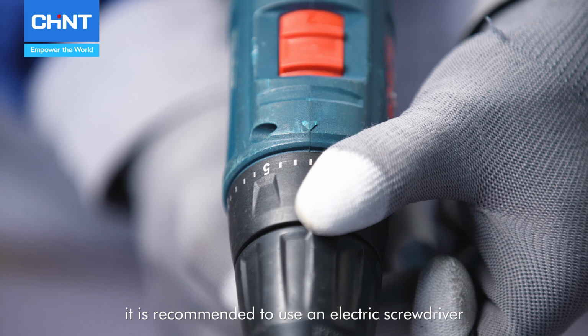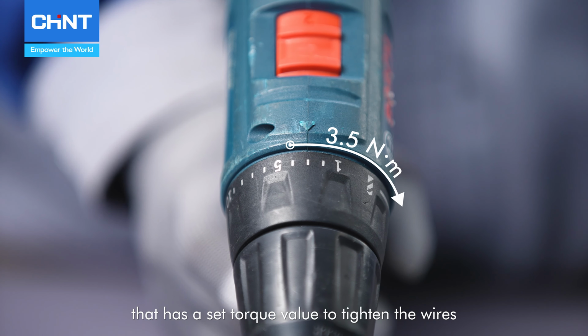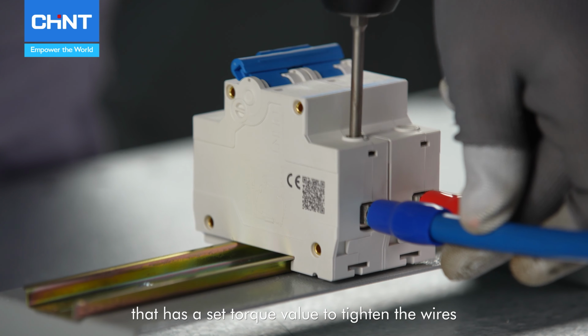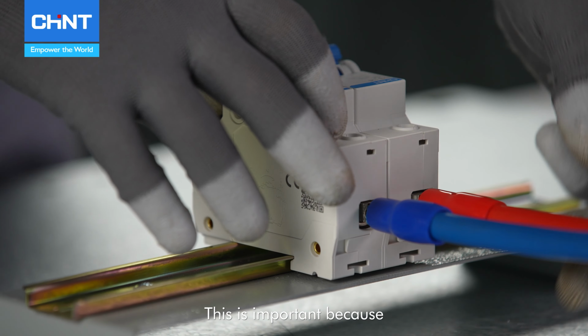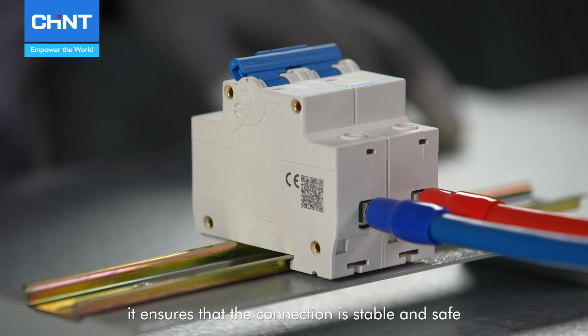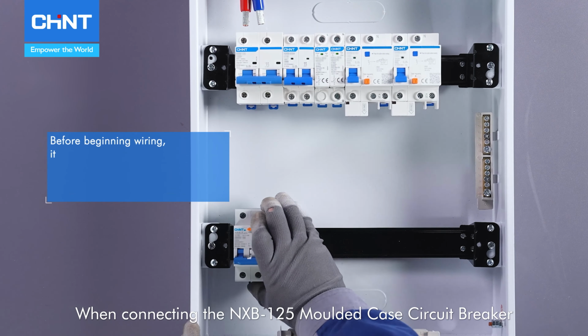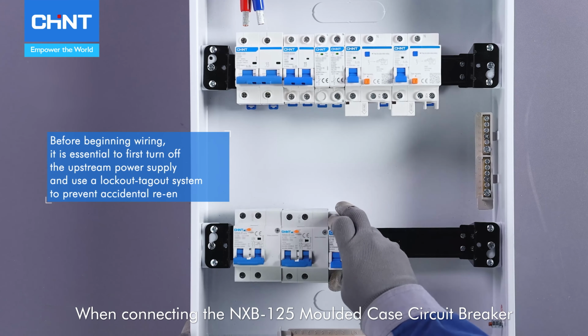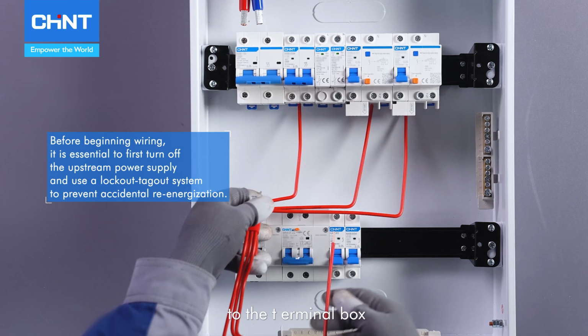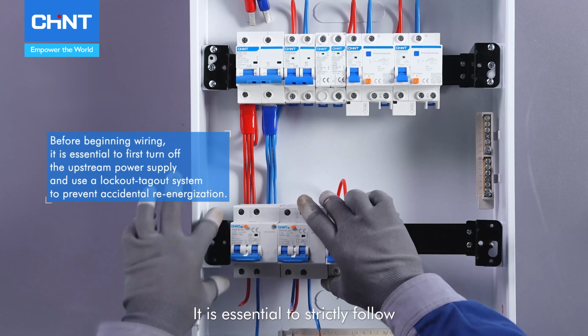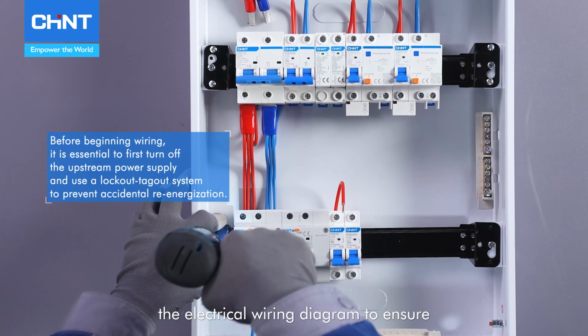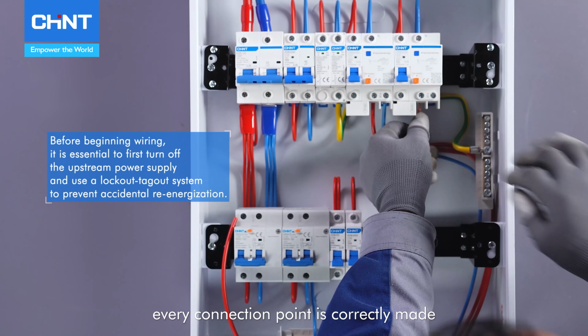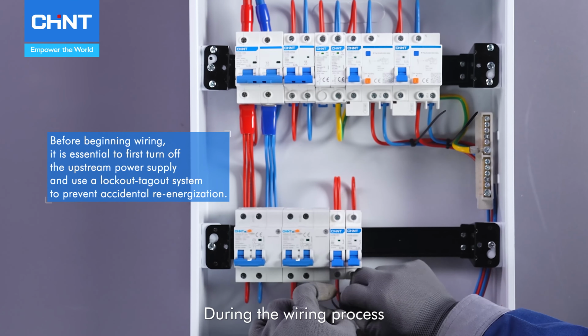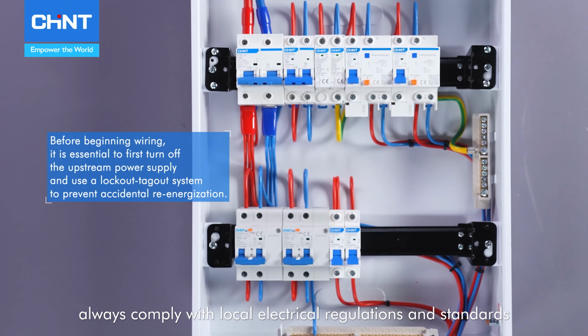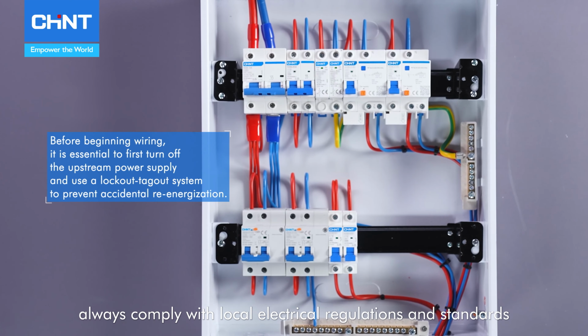Finally, it is recommended to use an electric screwdriver that has a set torque value to tighten the wires. This is important because it ensures that the connection is stable and safe. When connecting the NXB-125 molded case circuit breaker to the terminal box, it is essential to strictly follow the electrical wiring diagram to ensure every connection point is correctly made. During the wiring process, always comply with local electrical regulations and standards.